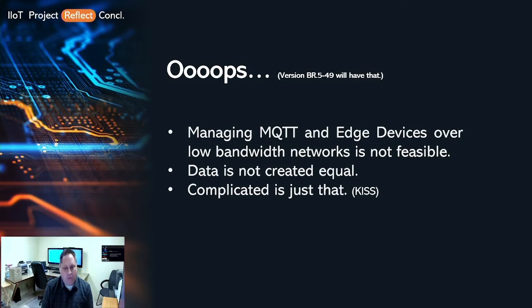Essentially, what you're doing with edge processing is moving the polling engine into the field. Now you have all of that polling, the tags, the configuration for that out in the field. And you're going from one centralized polling engine into dozens or hundreds of devices now that handle that polling. In our case, we have 245 edge devices in the field—I think upwards of 250 now. So when you go from one centralized polling engine to 250, you're adding a layer of complexity there.